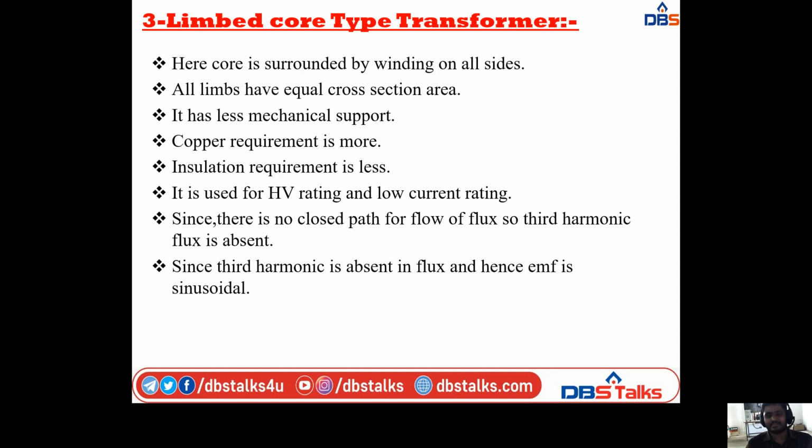Since there is no closed path for flow of flux, the third harmonic flux is absent in the three-limbed core-type transformer. And since the third harmonic is absent in the flux, the EMF is sinusoidal.